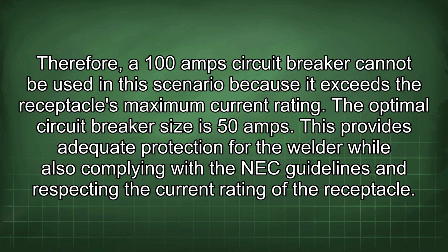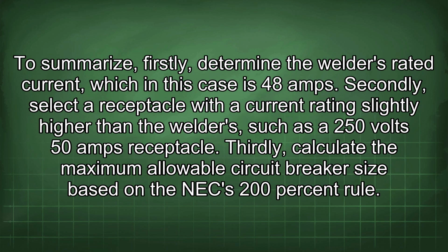The optimal circuit breaker size is 50 amps. This provides adequate protection for the welder while also complying with the NEC guidelines and respecting the current rating of the receptacle. To summarize, firstly, determine the welder's rated current, which in this case is 48 amps. Secondly, select a receptacle with a current rating slightly higher than the welder's, such as the 250 volts 50 amps receptacle. Thirdly, calculate the maximum allowable circuit breaker size based on the NEC 200% rule.